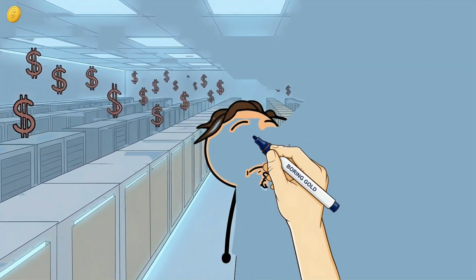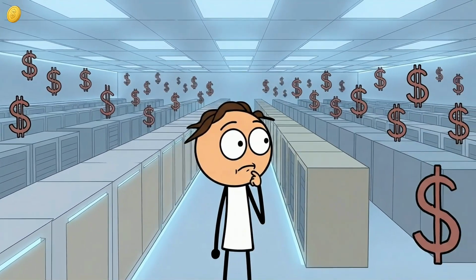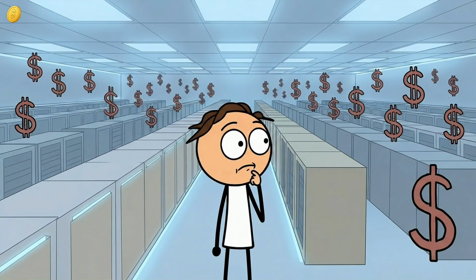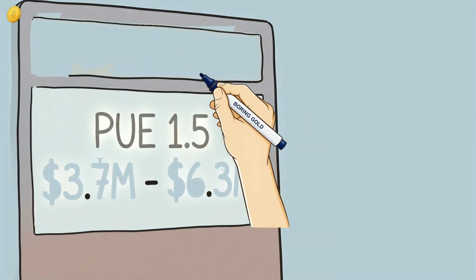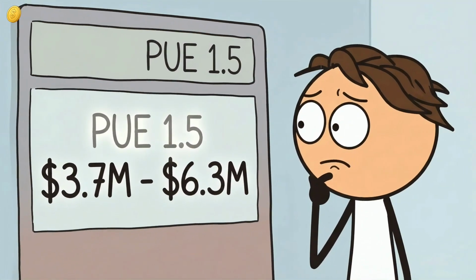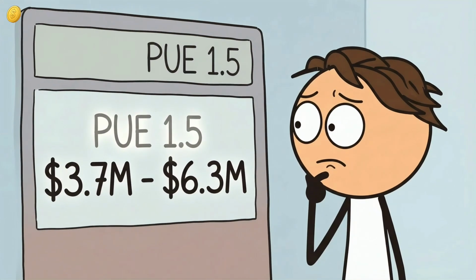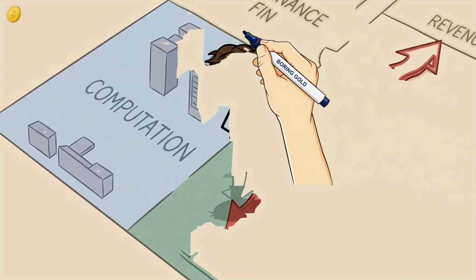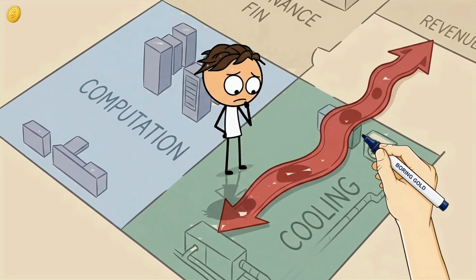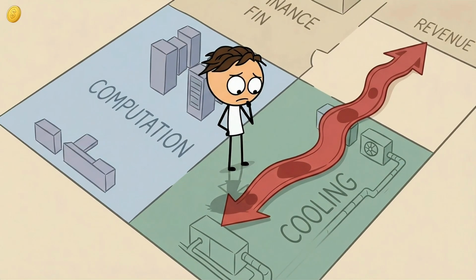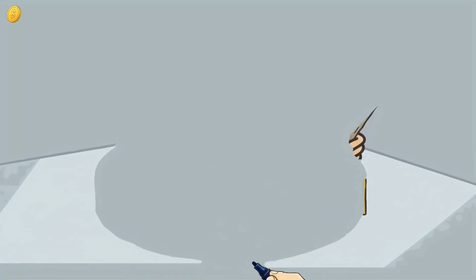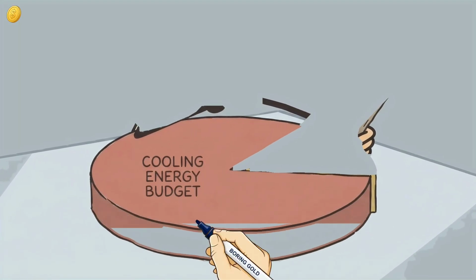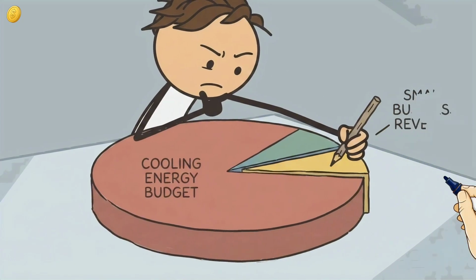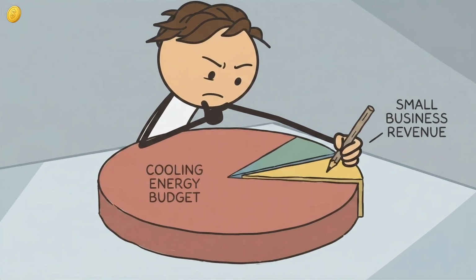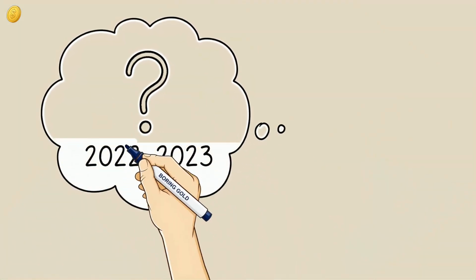At current U.S. commercial electricity prices of roughly 7 cents to 12 cents per kilowatt hour for large industrial consumers, a 10-megawatt AI data center running at a PUE of 1.5 spends between $3.7 million and $6.3 million per year purely on electricity required to cool the facility. Not to run the GPUs, to cool them. The cooling energy budget alone, at industrial scale, exceeds the total annual revenue of most small businesses. That is the cost of not solving the problem.